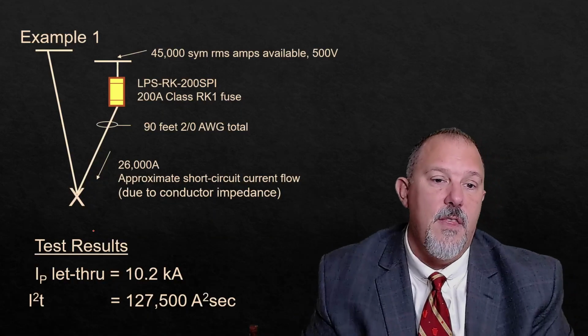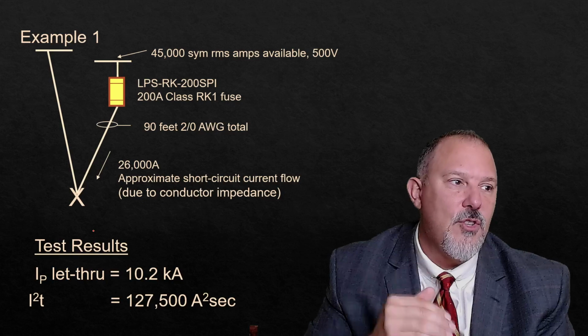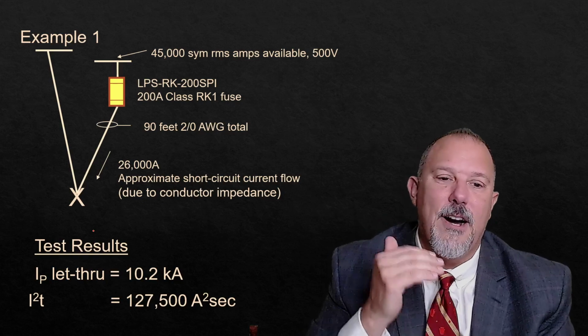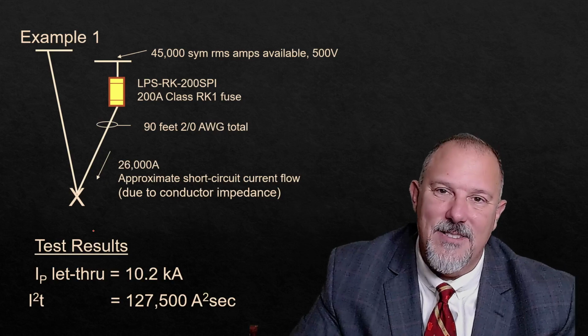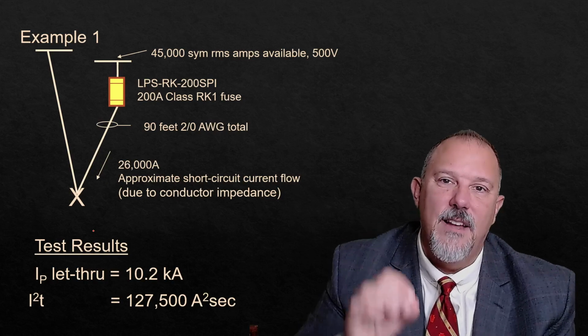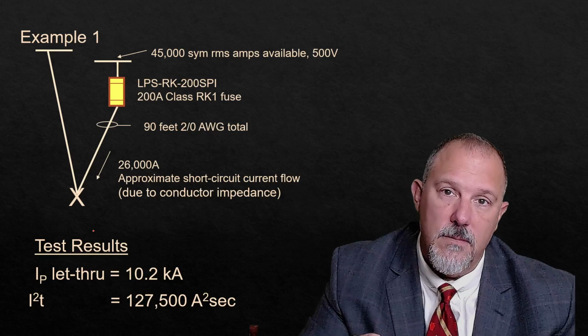Very slight movement of the entire conductor. That relieves the pressure off of the system. That's why you can have a disconnect switch that has a 200,000 amp short circuit current rating. Did it actually see 200,000 amps? No. Why? Because the protecting overcurrent protective device cleared it so fast that you did not see the magnetic forces of current because I reduced the peak. That peak let through was only 10.2 kiloamps. I only let through 127,000 amp squared seconds. Very little heat, very little magnetic forces.